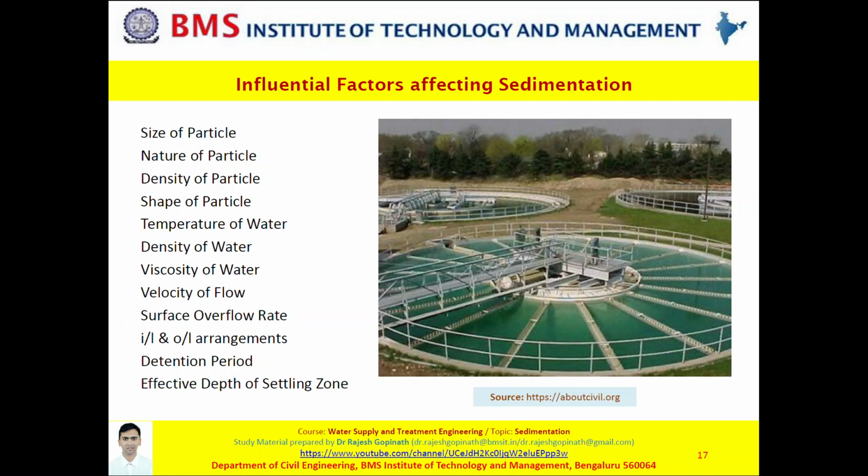Okay. Inlet and outlet arrangement also matters. Whether the water is entering in a smooth manner, whether the clearer water is exiting in a smooth manner. If your inlet and outlet arrangements are not apt, then there will be disturbance. There would be resettlement or rising of the settled solids. So obviously what happens is settlement will not happen gradually, settlement will not happen uniformly, and also the water which is exiting will contain suspended settleable solids.